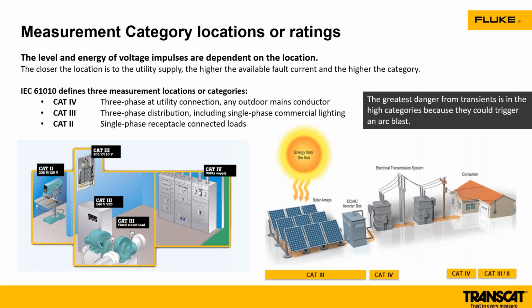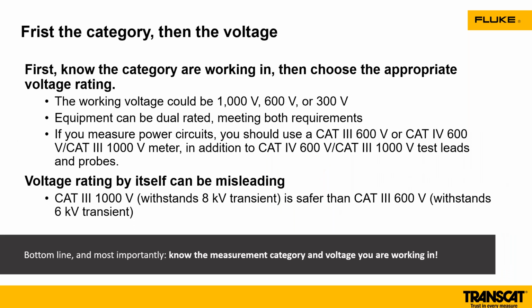Now, a lot of you are working in the solar industry and working in renewables. I like to highlight that in the category 3 environment, that's where your solar arrays are. That's all fixed devices. The category rating part of the standard now is a category 3. Going into the inverter, still a category 3, but once we get inside that inverter, we're now back to a category 4 environment, back to the utility side of that. And then going back from the utility to wherever that energy is being consumed. Great slide. Know your category ratings because it helps you choose the right equipment for that environment. So when you're working with 1,000 volt, 600 volt, or even 300 volt, we need to know what that is. Most DMMs and clamp meters are dual rated. They will meet a different category environment.